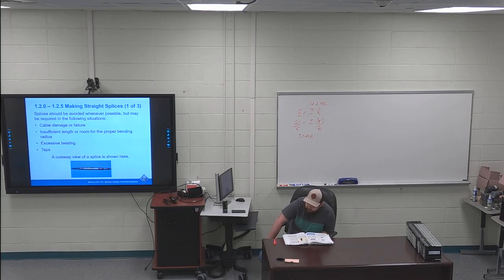Right-hand side of page 5, the paragraph right above the bullet points on the right-hand side, right above 121, that paragraph is highlighted. To finish off the splice and ensure complete protection over the entire splice, cover the entire splice with 4 layers of vinyl electrical tape, extending about 1/2 inch beyond the edge of the splicing compound. 4 layers of tape to finish off the splice.